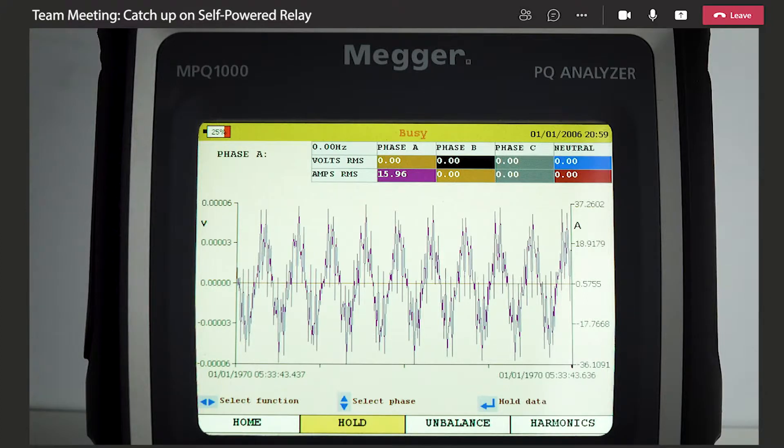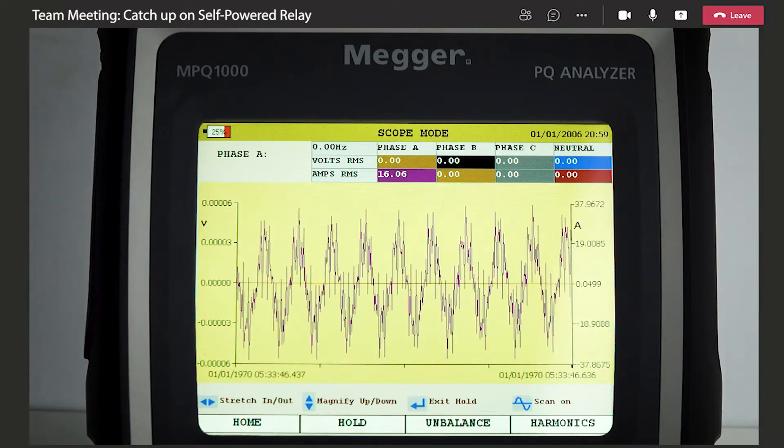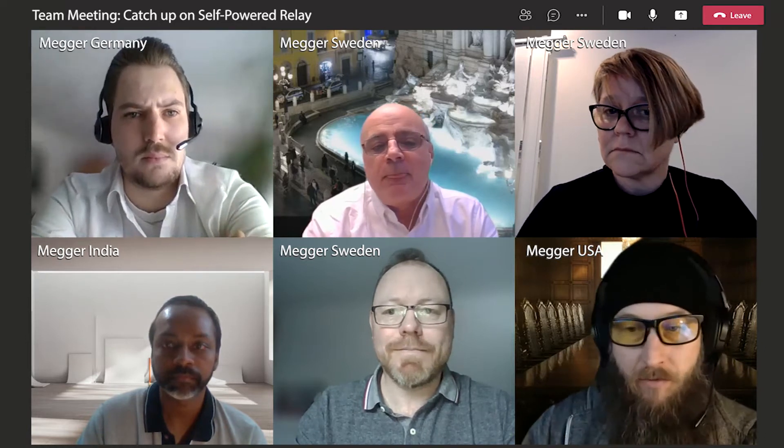Let me show you this and you will see what the signal looks like. Wow, that's an ugly signal — must be difficult to get accurate results. The problem is that these relays use a current that they draw the energy from, so these harmonics are generated by the relay and they enter the test set.